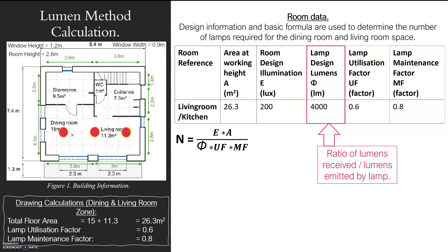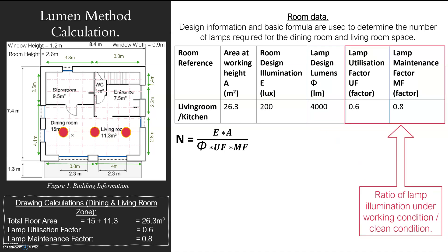Lamp design — this refers to the lights themselves. Once you know what lights you're getting, you can go to the manufacturer data and find the actual design lumens. From the manufacturer you can also find the utilisation factor and maintenance factor. Over the life of the lamp, the utilisation factor reflects how much light it will actually emit. With maintenance, consider whether dust will accumulate — if you're not cleaning it regularly, that will affect the amount of light it gives off.